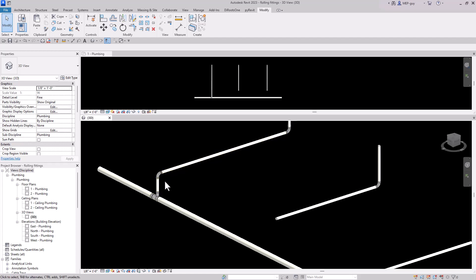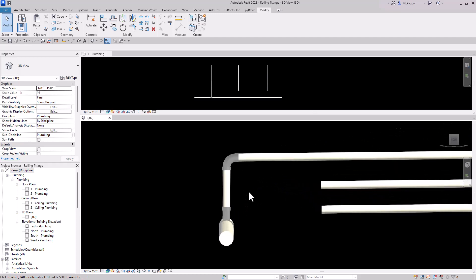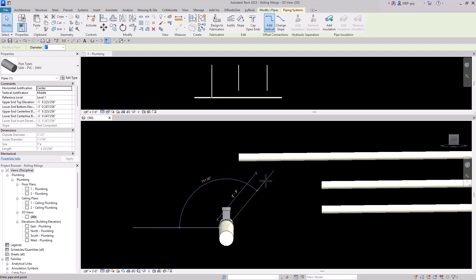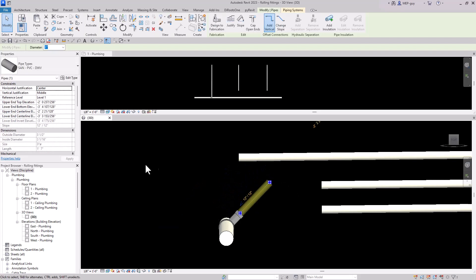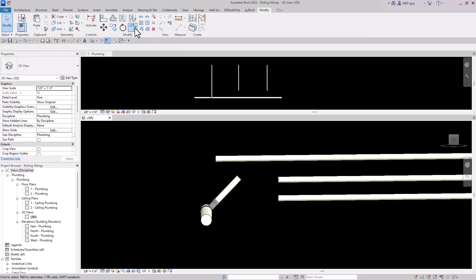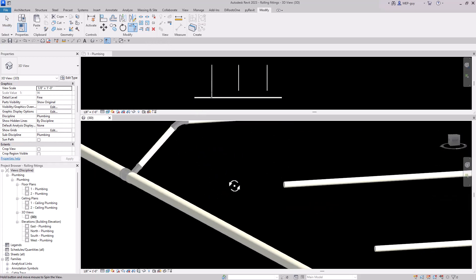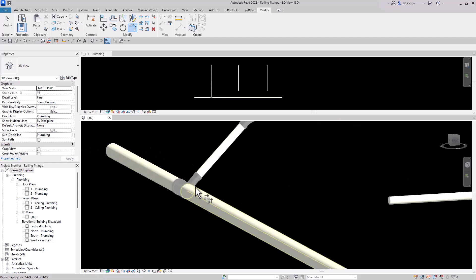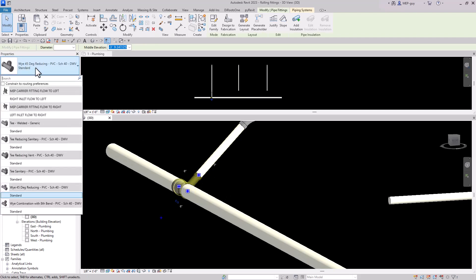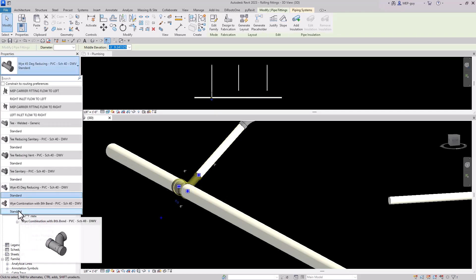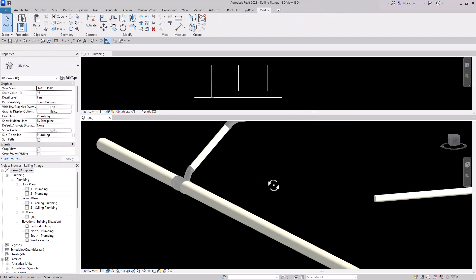We actually want to go to 45 degrees, so we'll use a similar technique. Click on the view cube again, zoom in, delete the fitting, and drag this piece to 45 degrees. From this view we can also use the Trim command — trim this piece into this piece — and now we have a nice rolling 45 degree angle into the main. Revit may draw the incorrect fitting, so click on it and change it to a Y combination fitting, and that looks perfect.